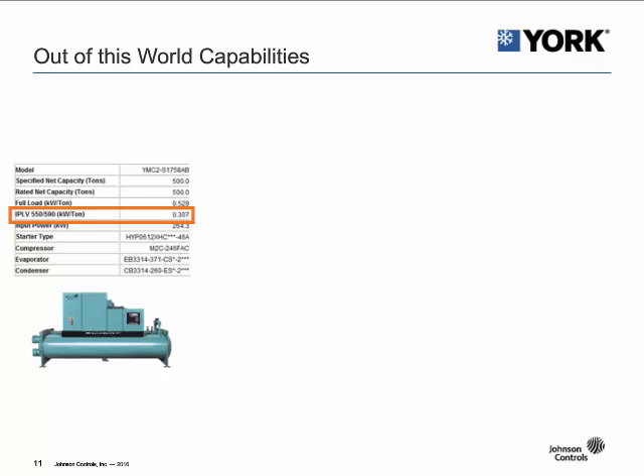Okay, and then that kind of goes hand in hand with the last question. Are there any chillers running like this in the market? Absolutely. So again, all of our YMC squared chillers, well over 1,000 in the field, can operate this way. So depending on the weather conditions that are seen at the building, you can absolutely foresee an inverted operation. And again, it's not just a cooling office building application. If a data center or a hospital utilizes higher leaving chilled water temperature, it gives more ability to operate inverted as the winter months come in.